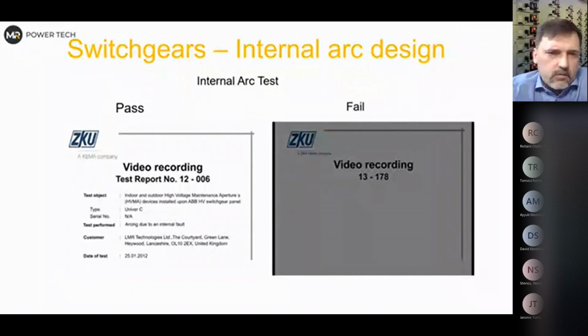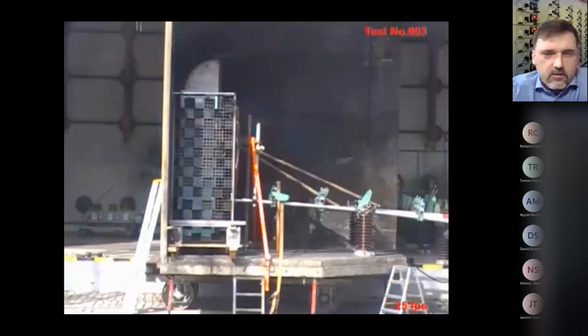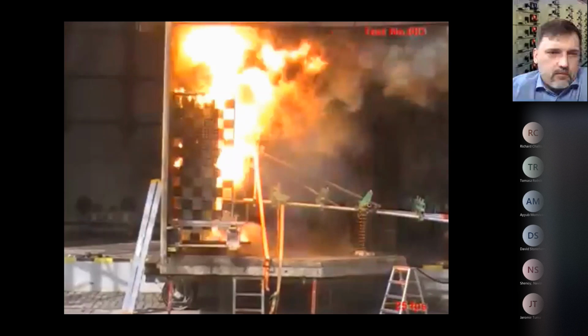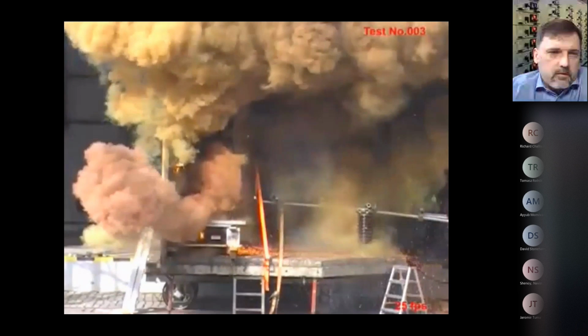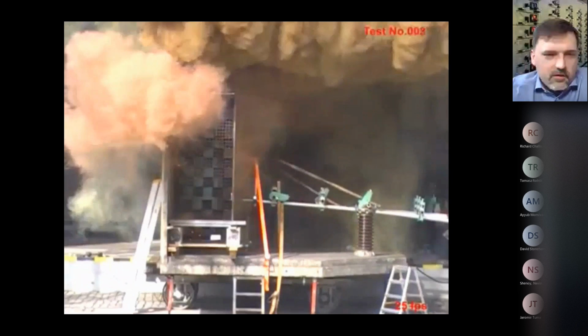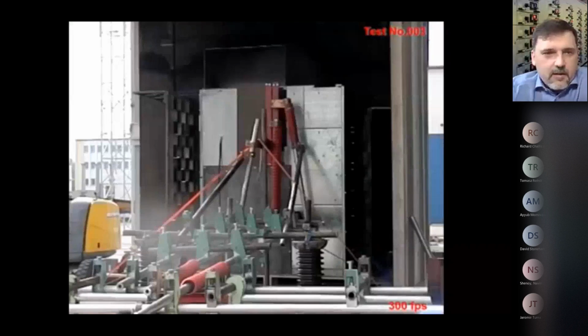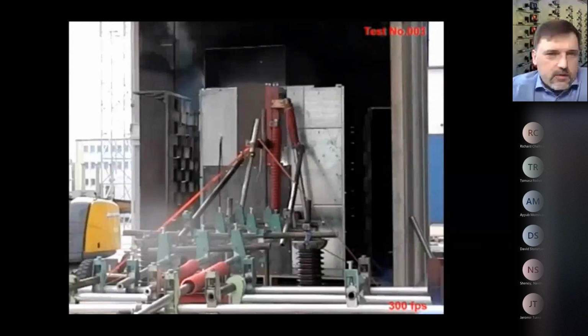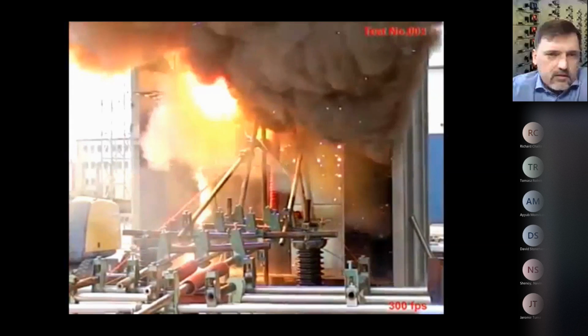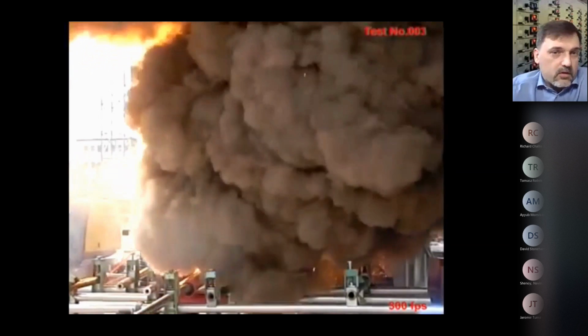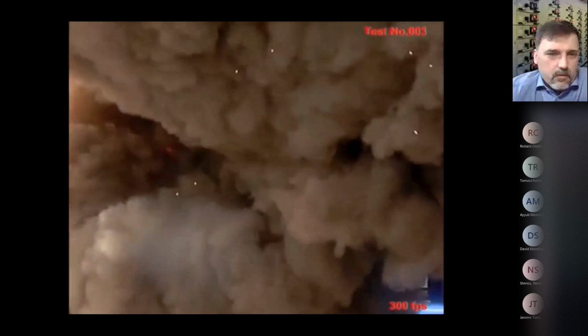And this is how it looks when you fail such a test. Yeah, it's straightforward. You don't have to be an engineer to see that this is not okay. But if you look in slow motion, you will see that, yeah, the arc was not confined inside. So you don't have any internal arc classification.